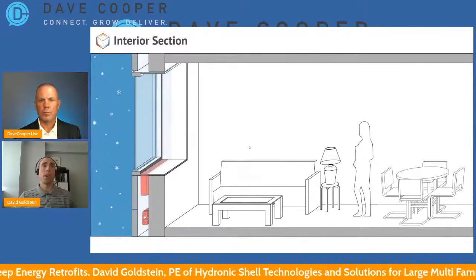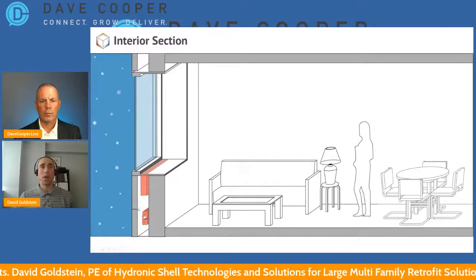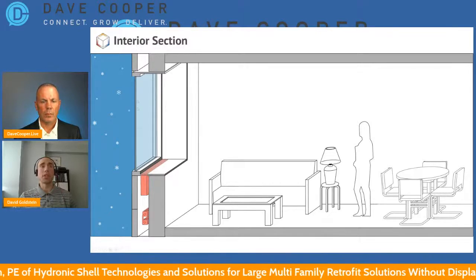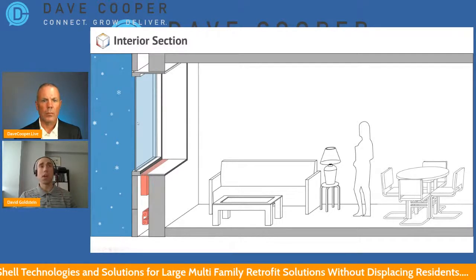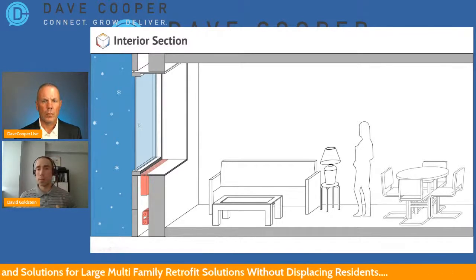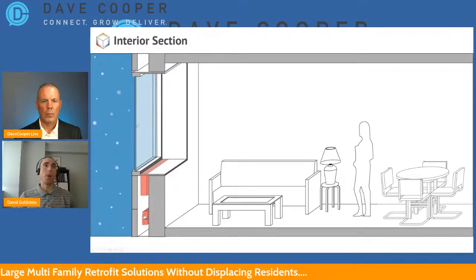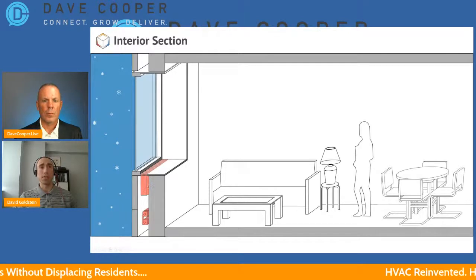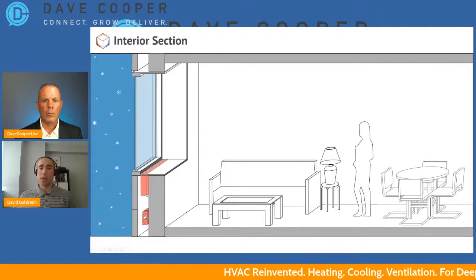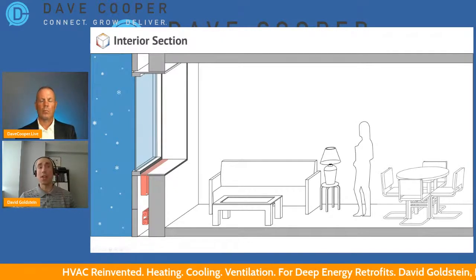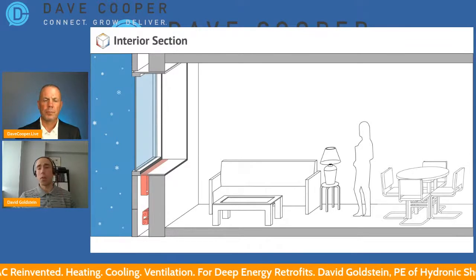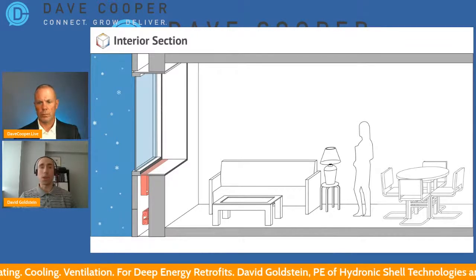So what we do after removing that window is install this new panel on the exterior - that super insulated panel with the integrated window. This all comes prefabricated from offsite, and we install that panel over the existing facade. Basically, we're leaving a cavity between the new panel and the existing facade, and it's within this narrow cavity, say roughly 8 inches, that we're running all of this HVAC, the ductwork and the piping.